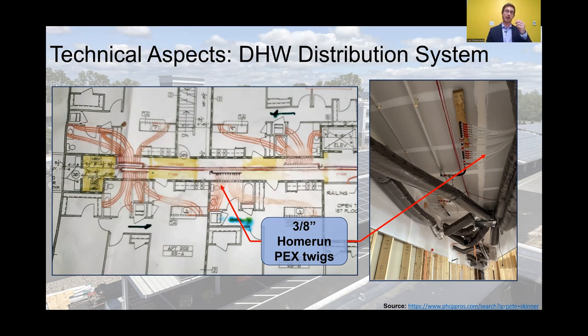These twigs run directly to each water appliance, and because of this, they're so skinny that there's so little water actually sitting in that pipe that as soon as you turn it on, the time it takes for hot water coming off the trunk line to get to your tap is shorter. And there's less water sitting in the line, so you're wasting less water, which means you need to heat less water, and you're getting less water usage while you're waiting for that hot water to come out.